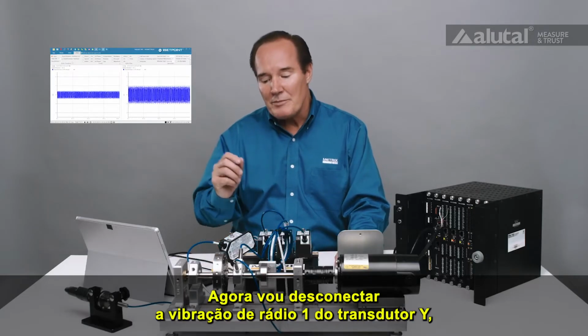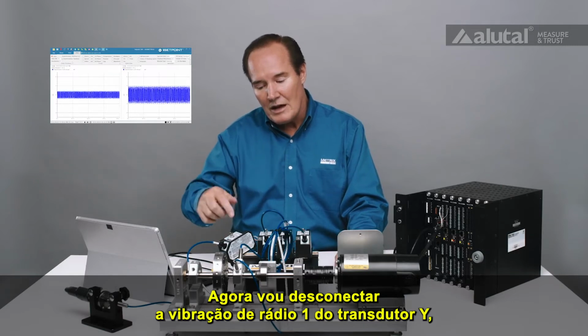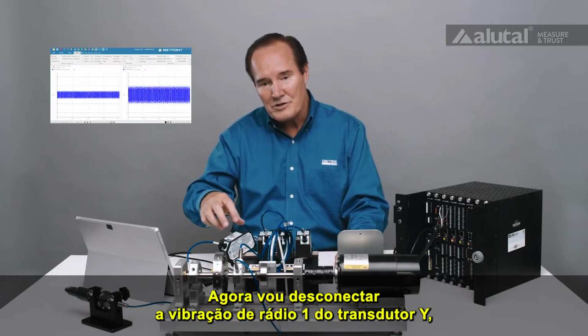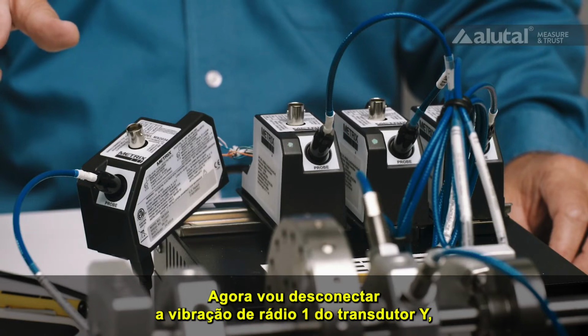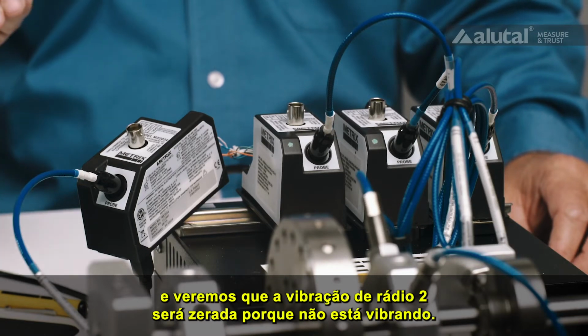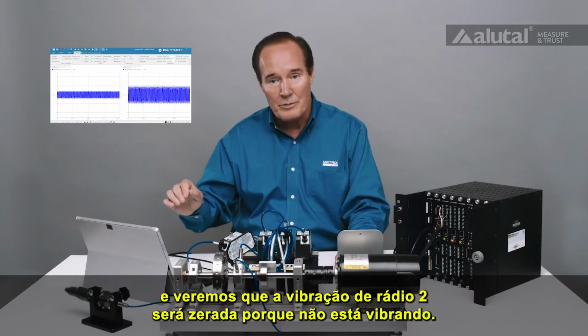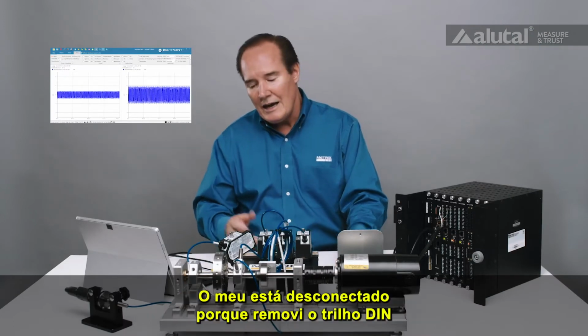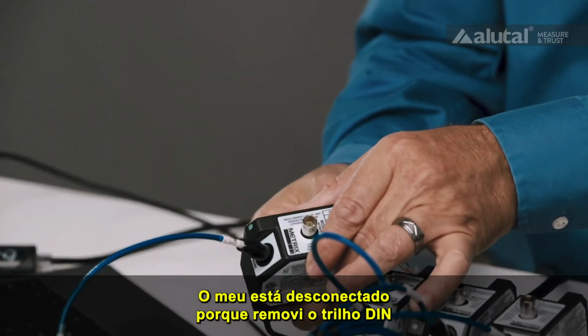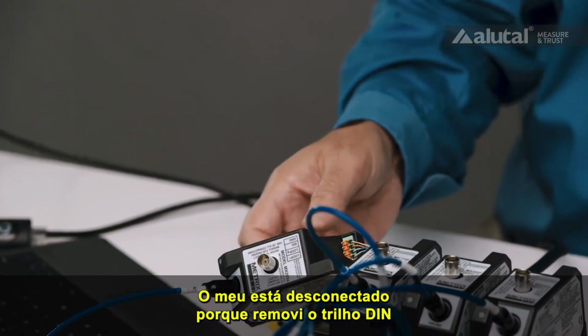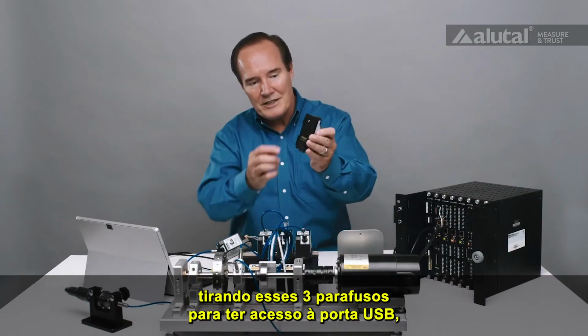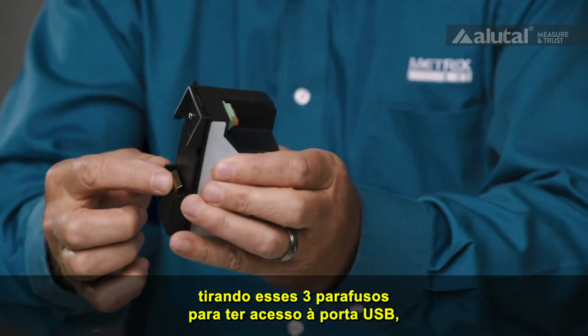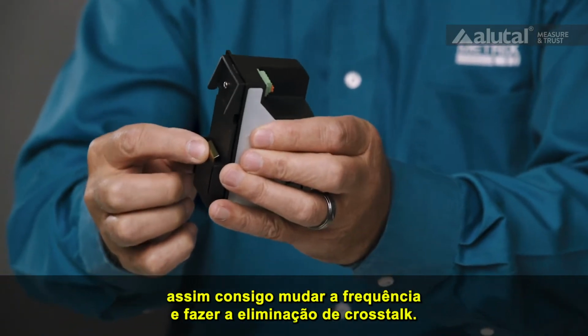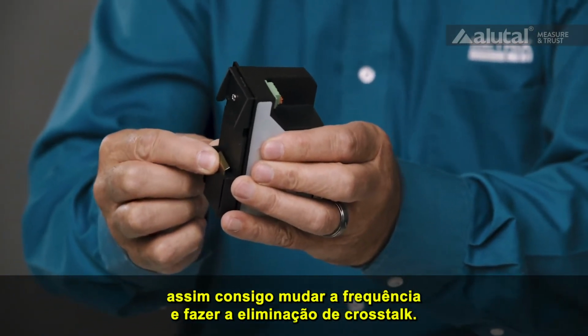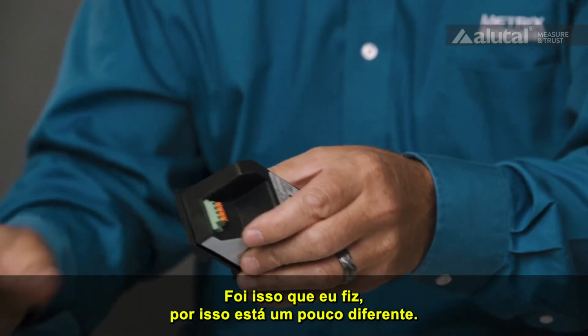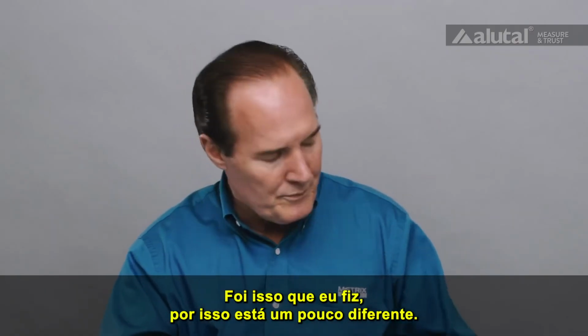What I'm going to do is disconnect the Y transducer, radial vibration 1, and we should see radial vibration 2 go to 0 because it's really not vibrating. I have this sort of disconnected because I've removed the DIN rail mounting, these 3 screws, so I can get to the USB port so I can change the frequency. I can use crosstalk elimination. So that's what I've done right now for my setup. That's why this is a little bit askew.